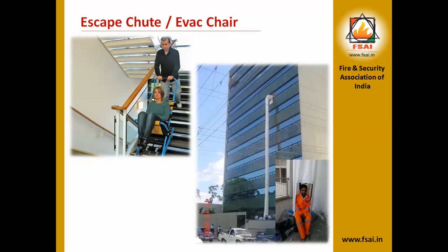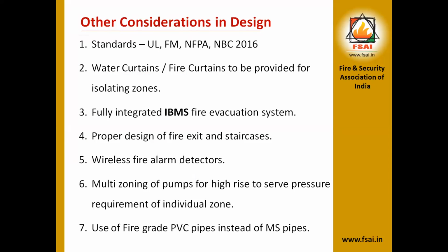There are many other considerations in the design to make the building a fireproof structure. The standards of UL, FM, NFPA and NBC 2016 are to be followed as per the category of the building, whether it is residential, industrial or commercial. Water curtains and fire curtains are to be provided for isolating zones to stop the fire from going from one zone to another. Then next is a fully integrated IBMS system, which is used for the evacuation of the system. So all the control is at one computer.